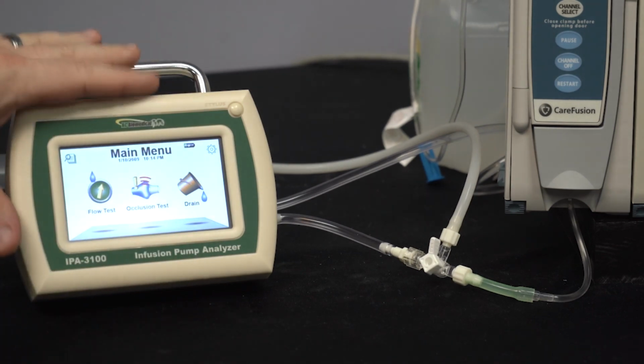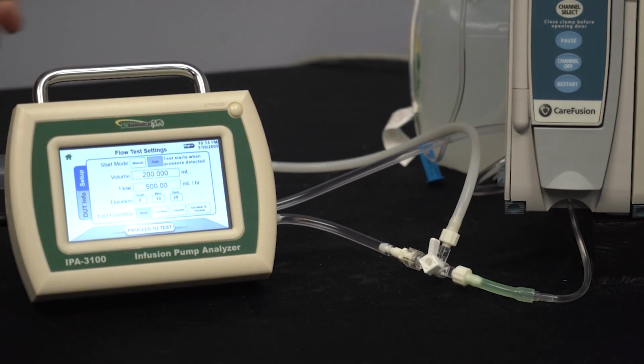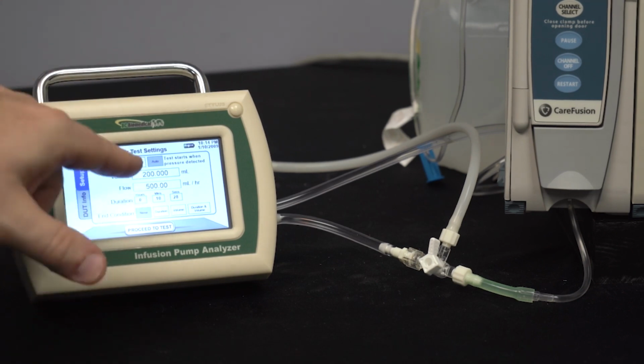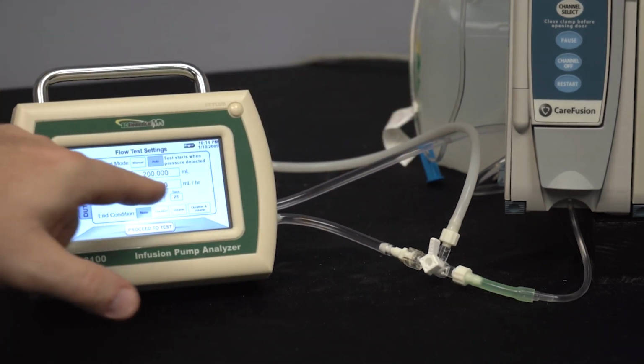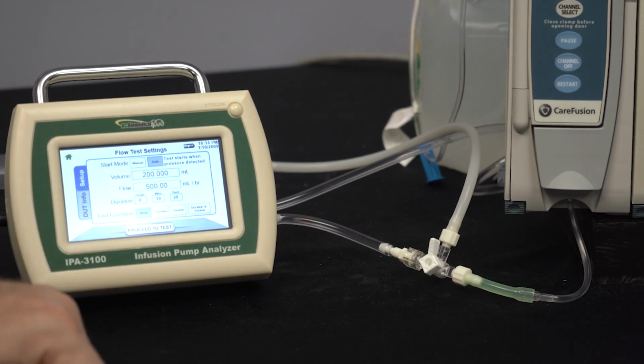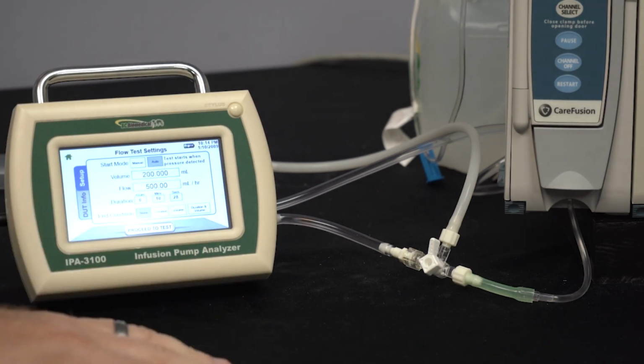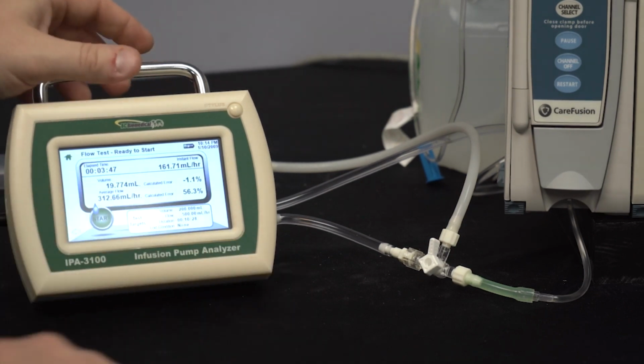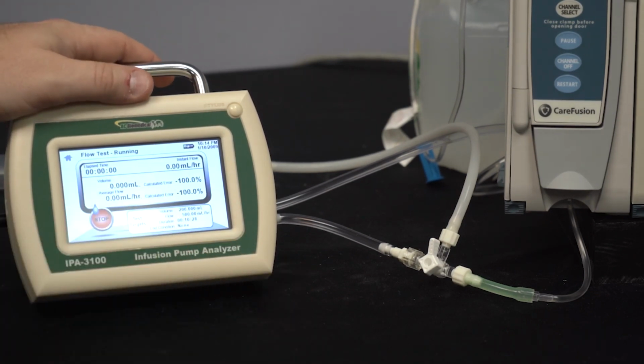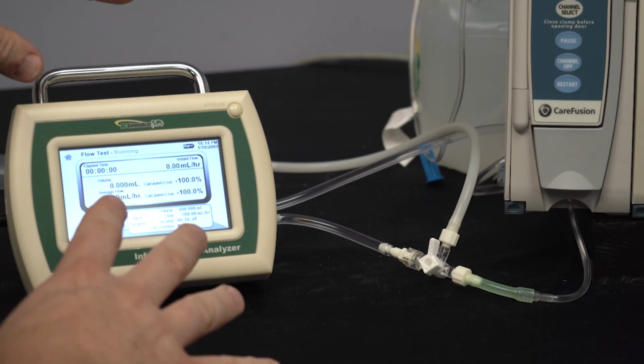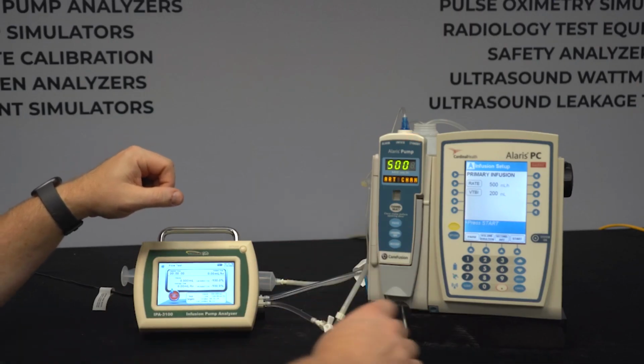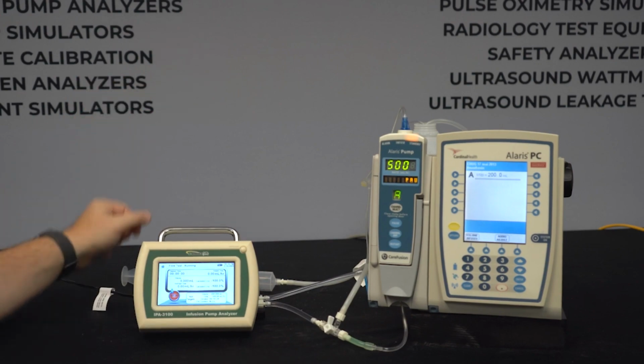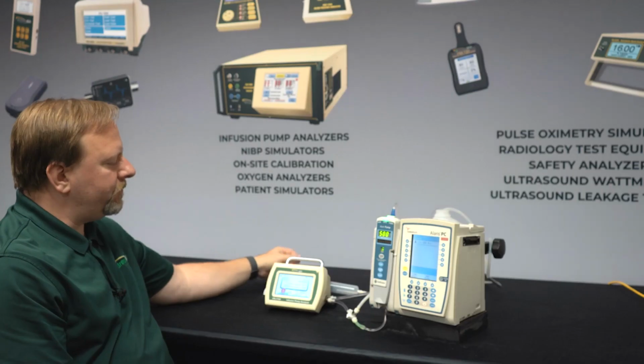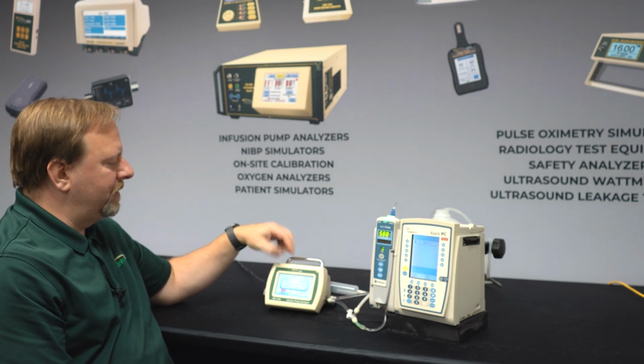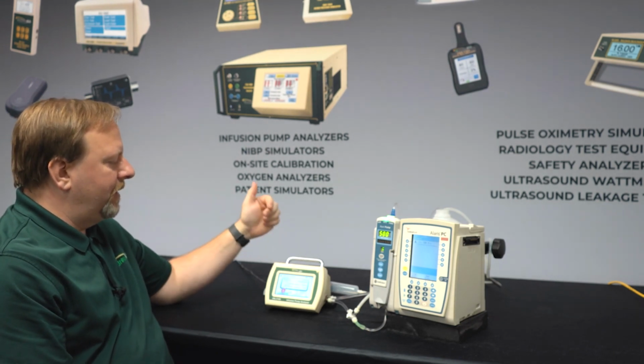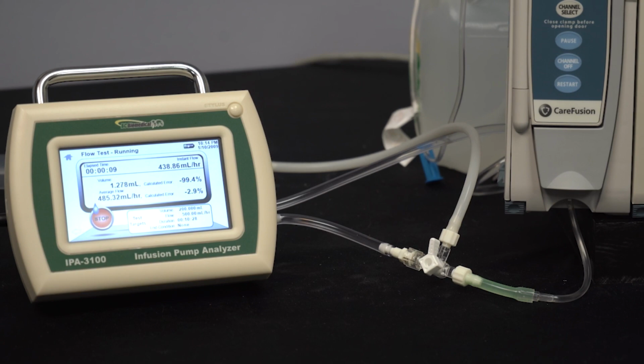So on the IPA 3100, I'll go into the flow test. Again, I'm not really worried about accuracy, but I'm still going to set it to the same settings. So I have 500 milliliters per hour for the flow rate and 200 milliliters for the dispense, even though we're not going to do that full dispense. Now, I'm going to start the test here, so it's ready to go. It's prepared. All I have to do is start the pump, and we'll start measuring our flow rate. So we can see we detected that flow. We're getting measurements on the screen, and everything seems to be running normally.